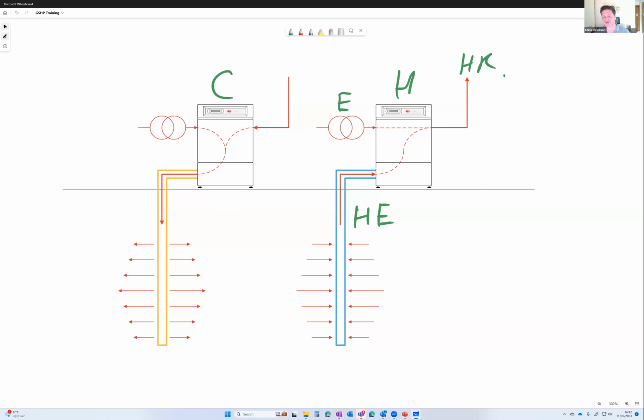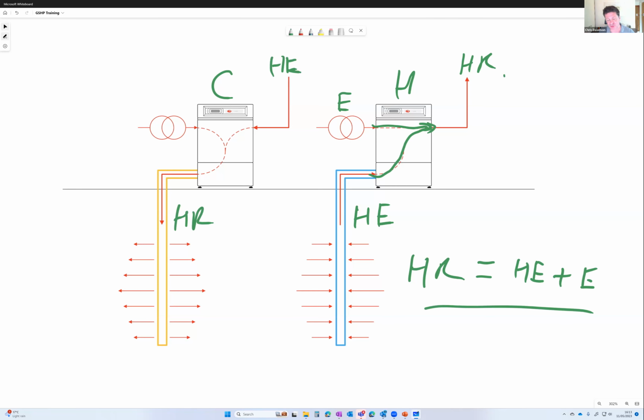In our heating system, the heat being rejected to the building is very close to equal to the heat being extracted from the ground plus the electrical energy, because very close to 100% of that electrical energy, through the forces of friction, ends up as heat. So heat of rejection equals heat extracted from the ground plus electrical energy. The opposite is true in cooling mode: we're now extracting heat from the building, the heat of extraction, and rejecting heat to the ground. The same expression holds, but now our electrical energy is being added to the energy taken from the ground. So in a very real way, the electrical energy in heating mode assists the heating of the building, and it hinders in cooling mode.